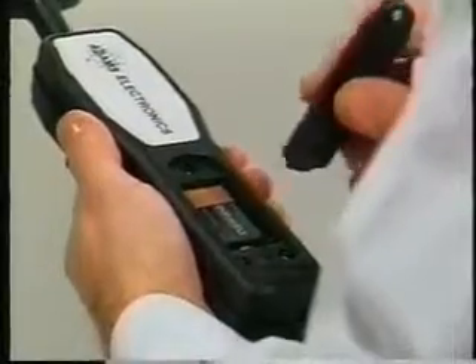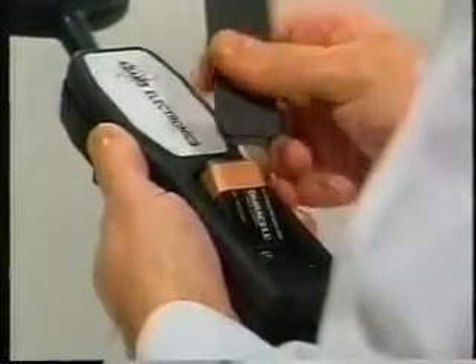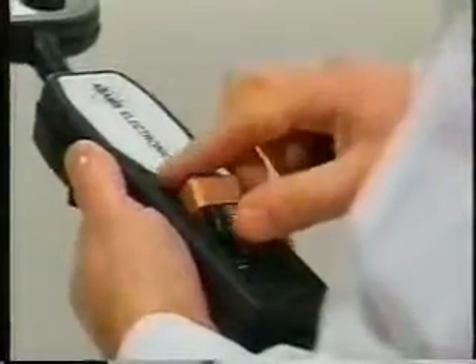To check or replace the battery, undo the screw on the battery compartment cover. This screw is self-retaining, so it will stay fixed to the battery compartment cover even when removed. Using the narrow end of the compartment cover, disengage the battery from the compartment by pushing backward and lifting up slightly. This will free the battery from the detector. You may then check the battery's power level using the battery's own checking system or a volt-ohm meter.